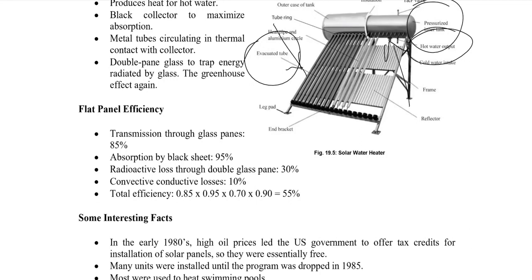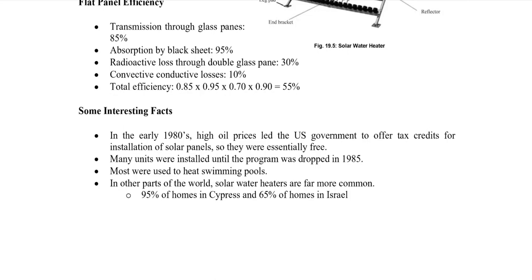For flat panel efficiency: transmission through glass is 85 percent, absorption by the black sheet is 95 percent, and radiative, convection, and conduction losses reduce overall efficiency to about 55 percent. Since solar energy is essentially free, 55 percent efficiency is quite good. Interestingly, in the early 1980s when oil prices were high in the United States, the government offered tax credits for solar panel installation, making them essentially free, and many units were installed until the program was dropped in 1985.